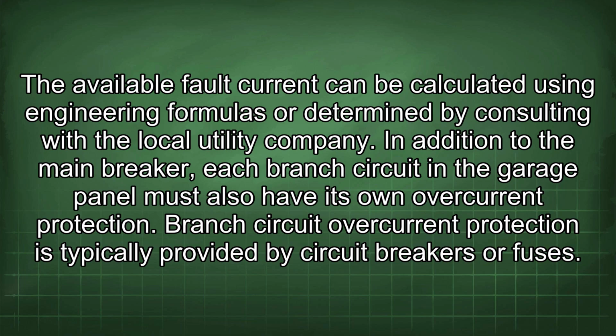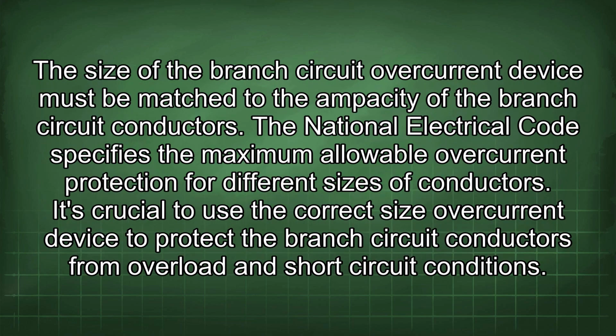company. In addition to the main breaker, each branch circuit in the garage panel must also have its own overcurrent protection. Branch circuit overcurrent protection is typically provided by circuit breakers or fuses. The size of the branch circuit overcurrent device must be matched to the ampacity of the branch circuit conductors. The National Electrical Code specifies the maximum allowable overcurrent protection for different sizes of conductors. It's crucial to use the correct size overcurrent device to protect the branch circuit conductors from overload and short circuit conditions.